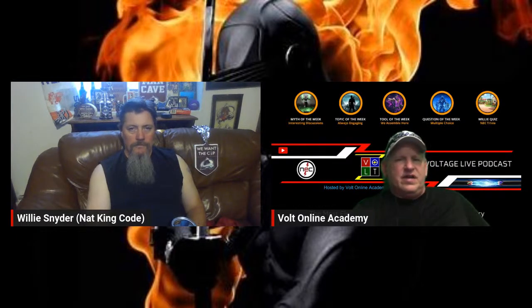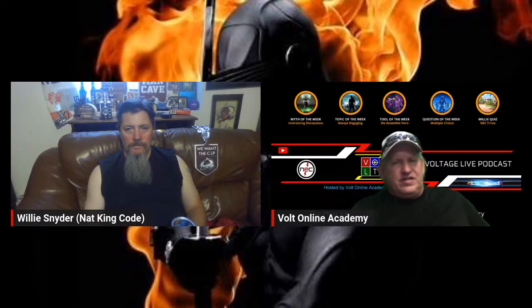It's like when we had the discussion, oh, this has been what, 2.5 years ago, and they were saying that there was an outlet there at the AC unit. And I said, no, there isn't. But just to be fair, let's say there is. Is that rated for a wet location? And they said, what the hell's that got to do with it? I said, well, when they do the listing and labeling of the equipment, they take not only the UL standards and other NFPA standards, but also the National Electrical Code into consideration. And if they're considering that to be an outlet in there, then it'd have to be rated for a wet location, just like the wiring and everything else that's outside.